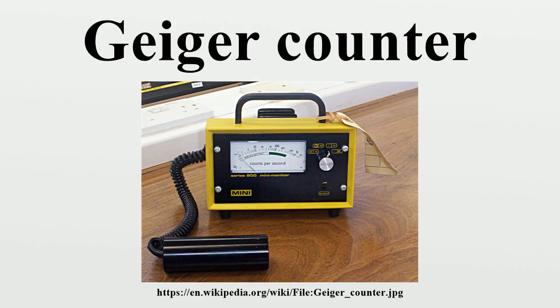Particle detection of alpha and beta can be used in both integral and two-piece designs. A pancake probe is generally used to increase the area of detection in two-piece instruments whilst being relatively lightweight.